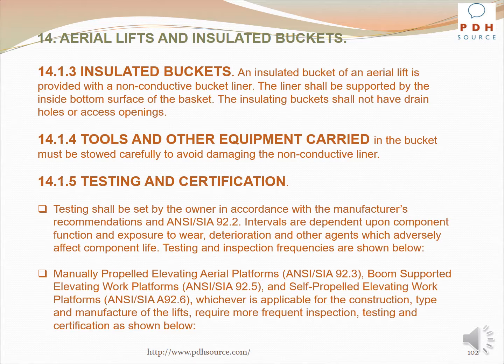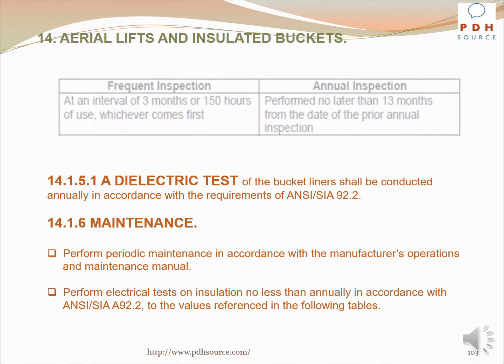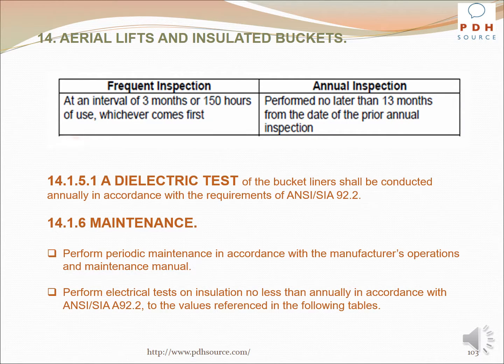Manually propelled elevating aerial platforms, ANSI SIA 92.3, boom-supported elevating work platforms, ANSI SIA 92.5, and self-propelled elevating work platforms, ANSI SIA 92.6, whichever is applicable for the construction, type, and manufacture of the lifts, require more frequent inspection, testing, and certification as follows. A dielectric test of the bucket liner shall be conducted annually in accordance with the requirements of ANSI SIA 92.2. Perform periodic maintenance in accordance with the manufacturer's operations and maintenance manual.